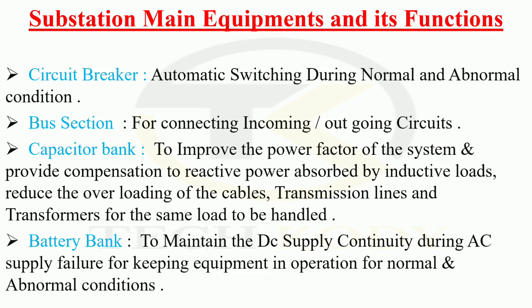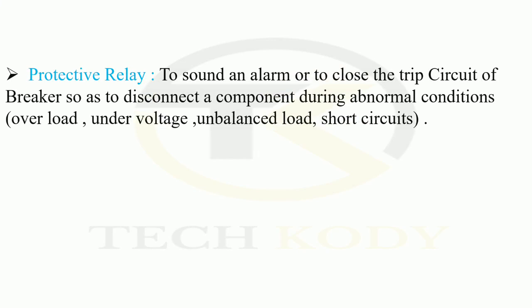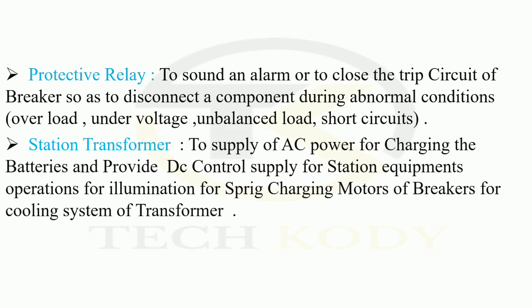Battery banks: to maintain the DC supply continually during AC supply failure, for keeping the equipment in operation under normal and abnormal conditions. Protection relay: to sound an alarm or close the trip coil of the breaker so as to disconnect a component during abnormal conditions — that is overload, under voltage, unbalanced load and short circuits. Station transformers: to supply AC power for the charging of the batteries and provide a DC control supply for the station equipment, operation and illumination, spring charging motors of the breakers, and cooling system of the transformers.